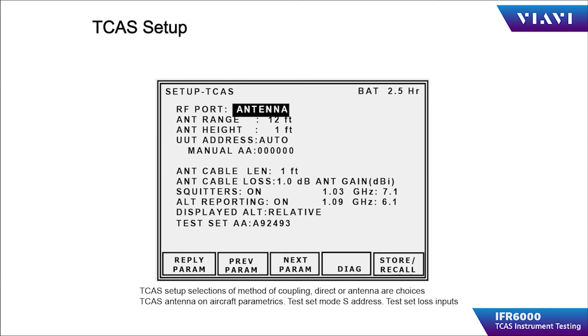Pressing the next parameter or previous parameter soft key will move the cursor to the next or previous operator input. Select a suitable location for the test set antenna so that the aircraft TCAS antenna has a clear line of sight view and is free from obstructions that will cause RF reflections.